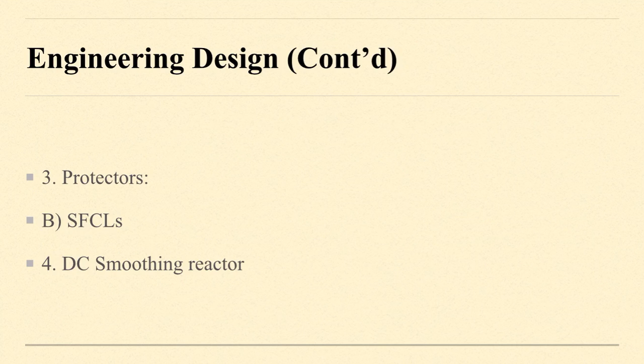Next, it's SFCL, superconducting fault current limiter. Using fault current limiting technology, SFCLs are invented. Low impedance is maintained in SFCLs while the system is healthy, and thus additional loss is low enough, and while a short circuit fault occurs, SFCLs will convert to high impedance quickly to limit short circuit current, and at the same time overcurrent is avoided. Next is DC smoothing reactor. It's actually designed for lightning protection and reduction of harmonic current.